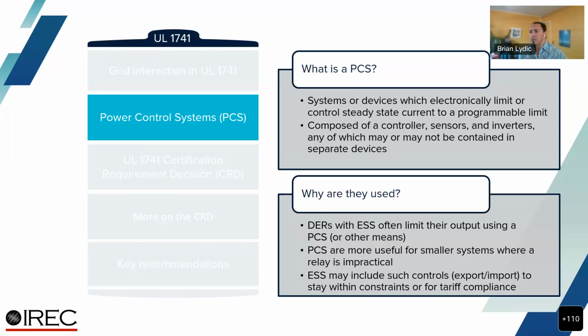These can be used alone or in conjunction with other means of controlling export, like utility grade relays, which can trip a DER off if it exceeds a certain export level. But power control systems are generally very low cost devices compared with relays, and they can be certified, which makes them desirable for interconnection processes, since certification makes verifying their capabilities very easy.